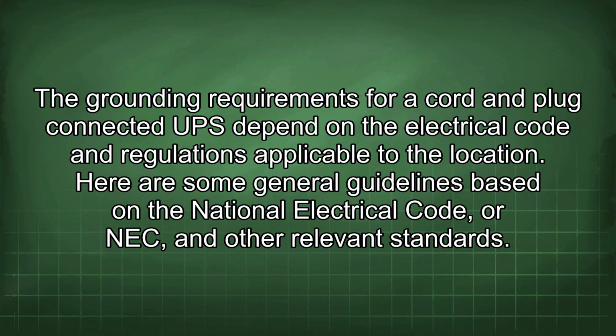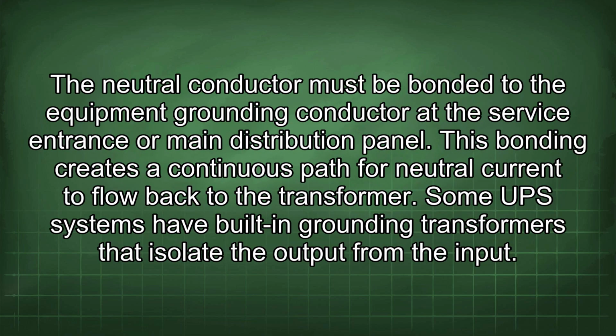Grounding requirements for a cord and plug connected UPS depend on the electrical code and regulations applicable to the location. Here are some general guidelines based on the National Electrical Code, or NEC, and other relevant standards. The neutral conductor must be bonded to the equipment grounding conductor at the service entrance or main distribution panel. This bonding creates a continuous path for neutral current to flow back to the transformer.